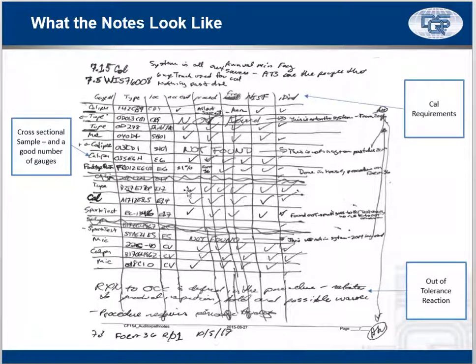I have the location I found them. I had whether acceptance criteria was there. They had procedures for calibration. The frequency was defined. It was traceable in this. And the gauges were identified. There you go. And then when something was off, I have a little AR. That's how I mark my ARs. I have a little statement here about out of tolerance conditions, and I had something on document control that I was looking at. That's it. You don't need extensive notes. This is roughly 2 hours of auditing a calibration process. And you can see it was done on about half a page of notes.